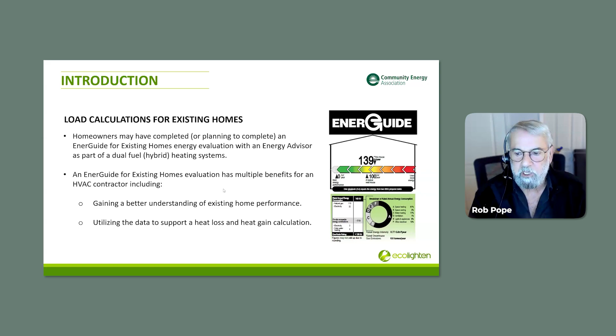So you take the HOT 2000, which is what the energy advisor is using, and you can do one of two things. You can take that information raw and input it, marrying it to a program called Volta Snap, which is CSA approved. It's a verified software, and that will give you the CSA F280-12 output, the load calculation.